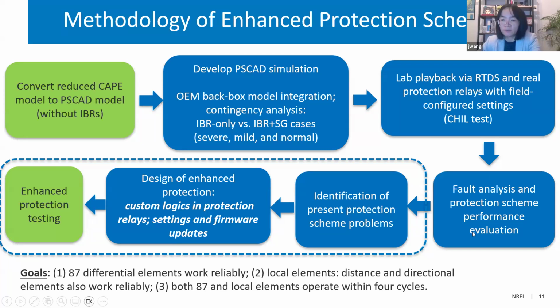Then we ran through all the different fault analyses and summarized what the challenges are, and then we propose the enhanced protection, including customized logic, relay settings, and logic updates. And finally, we validate those enhanced protection logics we propose to our partner. Our goal is to have the 87L differential element and also the local elements such as distance and directional elements work reliably and make the decision within the first 4 cycles. Then it will provide reliable protection for this transmission line with so many IBR plants.